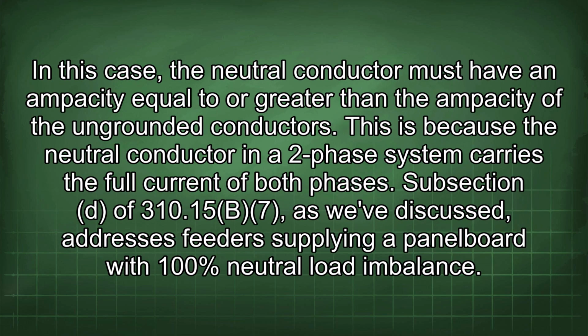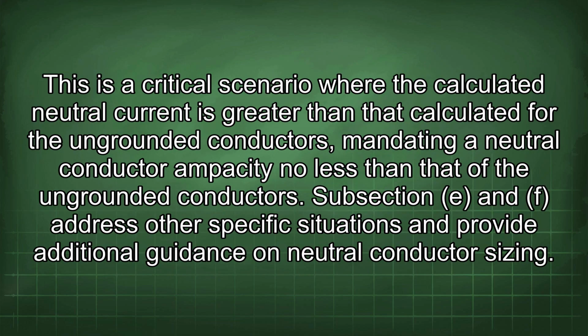Subsection C of 310.15(B)(7) addresses situations where the neutral conductor is used in a 3-wire circuit derived from a 2-phase system. In this case, the neutral conductor must have an ampacity equal to or greater than the ampacity of the ungrounded conductors. This is because the neutral conductor in a 2-phase system carries the full current of both phases. Subsection D of 310.15(B)(7), as we've discussed, addresses feeders supplying a panelboard with 100% neutral load imbalance. This is a critical scenario where the calculated neutral current is greater than that calculated for the ungrounded conductors, mandating a neutral conductor ampacity no less than that of the ungrounded conductors. Subsections E and F address other specific situations and provide additional guidance on neutral conductor sizing.